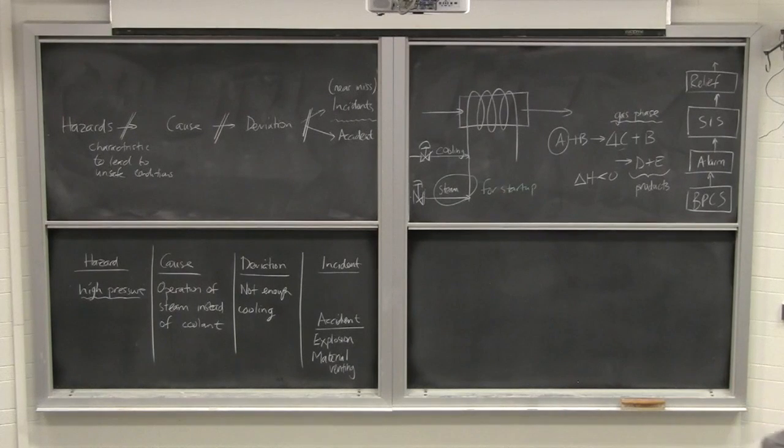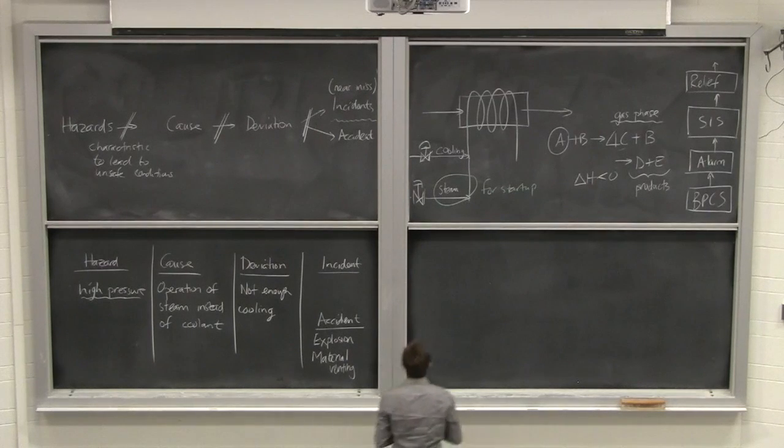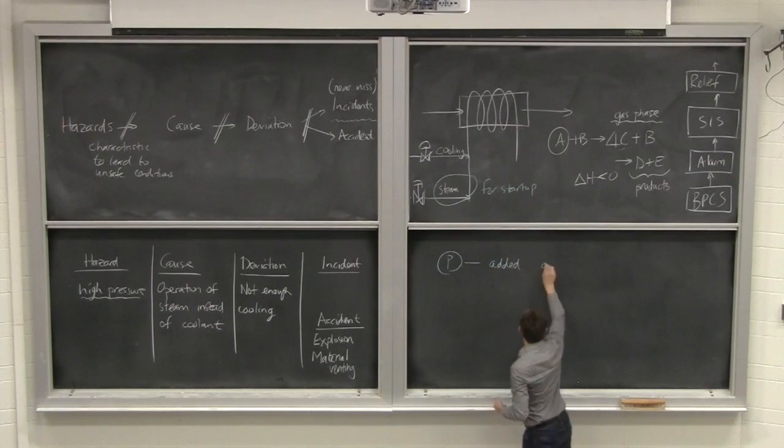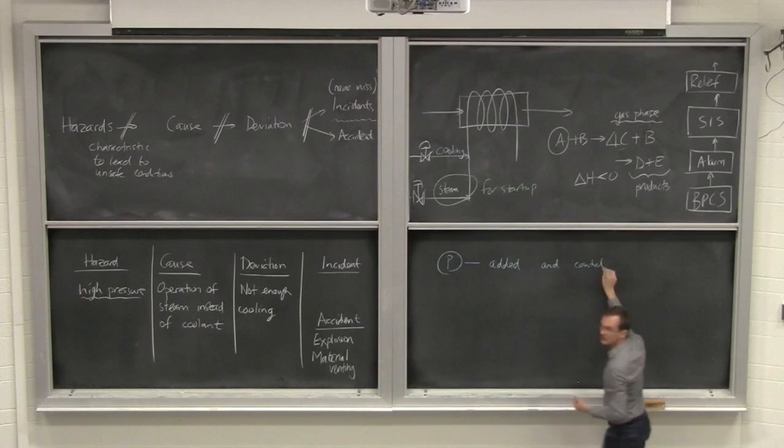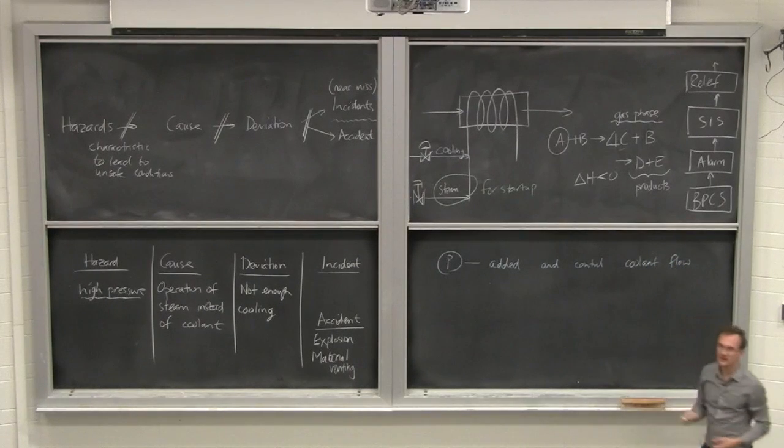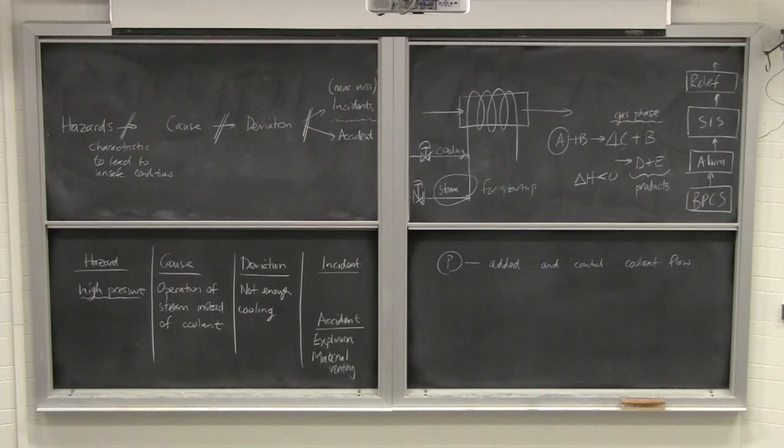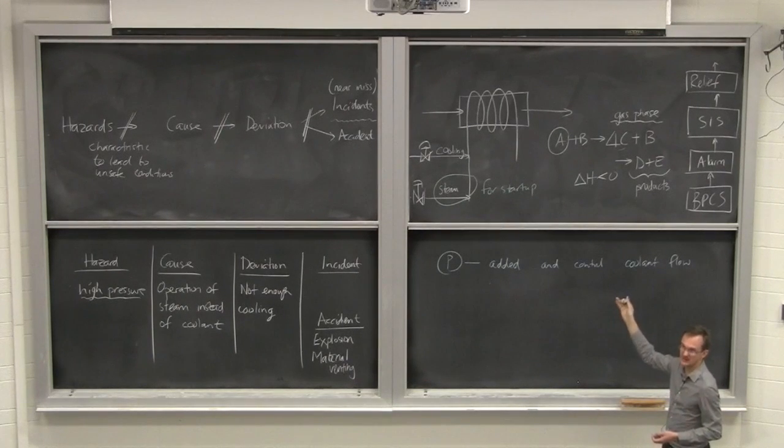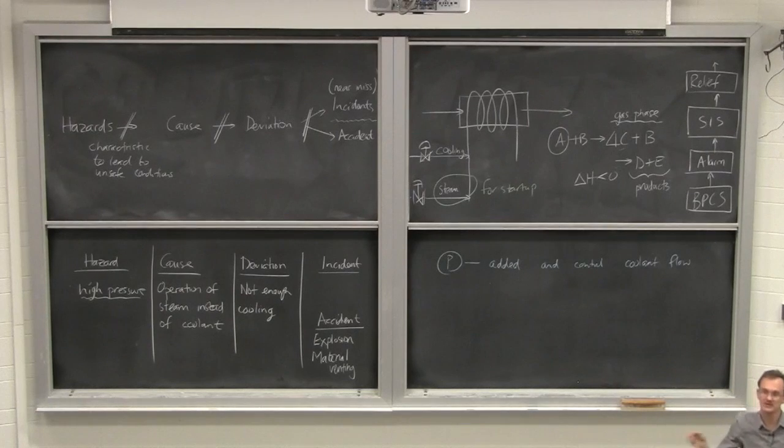Okay, some suggestions from some groups. P added. So you add a pressure sensor. And then you control coolant flow. Okay, let's presume that that was there, in fact. The same scenario could still play out with the pressure sensor there and to control the coolant flow. What could have happened is that that coolant flow is open to try and reduce the pressure, but the steam is still going.